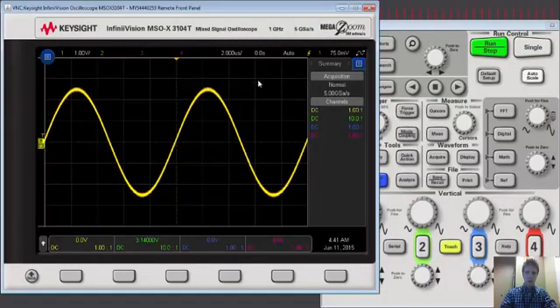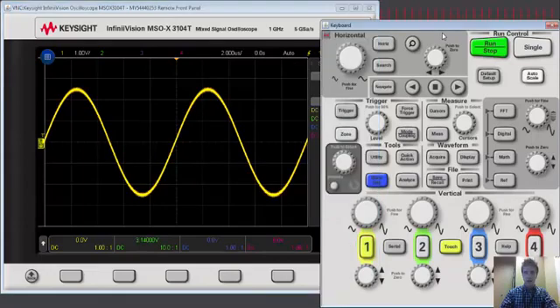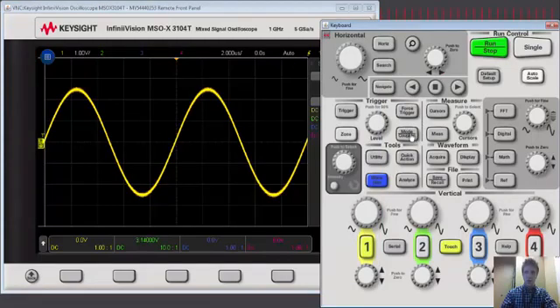What we notice on our screen in the top right corner it says auto which signifies we're in automatic triggering mode. To change that triggering mode we can do so a variety of ways. On the dedicated hard keys on the right side of the instrument we can access the trigger mode coupling menu button.